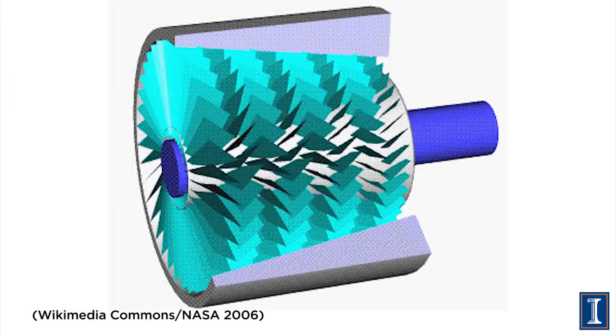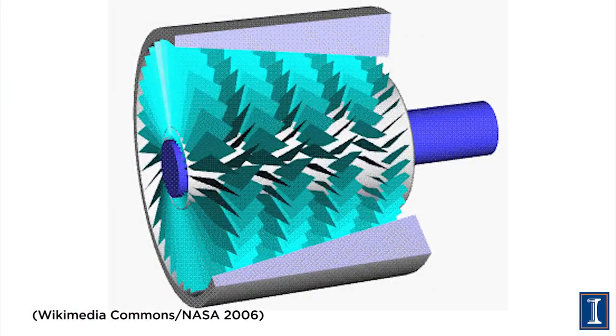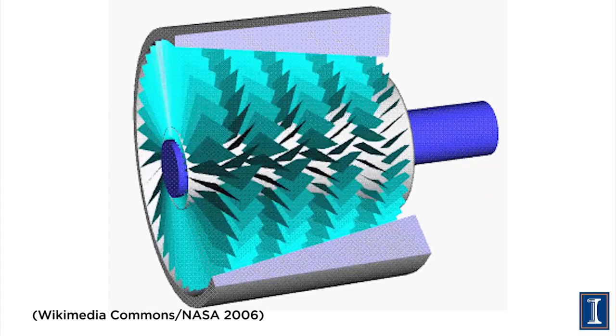This contraption called the turbine that has the stators and the rotors — the tolerances are small, the balance is precise. And if we put a whole lot of impurity, of scale, of things building up over time as this thing is constantly used year after year, decade after decade, you could destroy it. So you really want high purity water to go through this system.